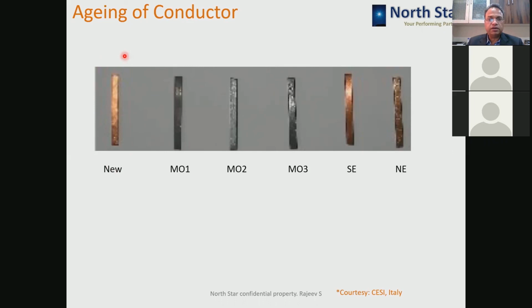This is a new conductor. This is with mineral oil. These three samples are with mineral oil aging test. Okay, you can see these got blackened. This is with synthetic ester and this is with natural ester. So comparatively, if you look at this, they are in much better shape as compared to the mineral oil system. So on the conductor also, the aging effect is very less with natural and synthetic esters.